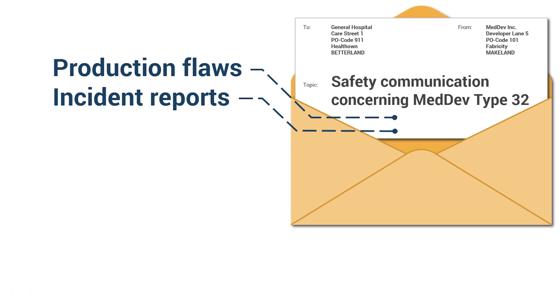And for corrective maintenance, repairs, there should be a procedure to register the malfunction and for releasing the device and putting it back in use after it has been repaired. And even if there were no adverse events, the hospital might sometimes be notified by a manufacturer that there's something wrong with a product, maybe due to a recently discovered production flaw, or because the same device very often malfunctioned in another hospital and the manufacturer decided to take the device off the market for a while to investigate if there's something wrong with the device or if the other hospital did something wrong.